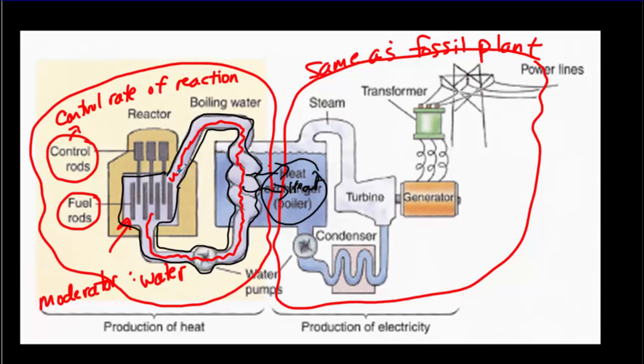The moderator, this water, will mostly remain as a liquid because the pressure is so high that it holds those water molecules together. And then, of course, once the heat is drawn out into the heat exchanger, the water is cooler down here and then it's pumped back into the chamber to be reheated. So this cycle here is very much like this cycle here. But in a nuclear plant, we want to isolate these two separate cycles so that we don't have radiation contamination.